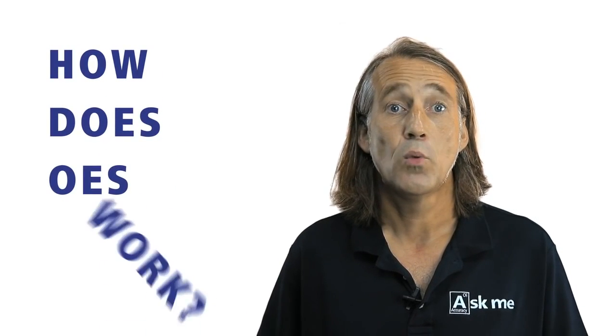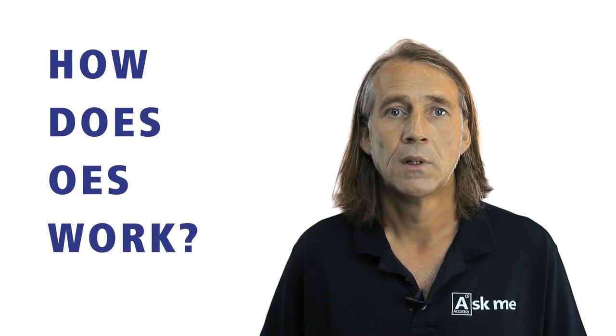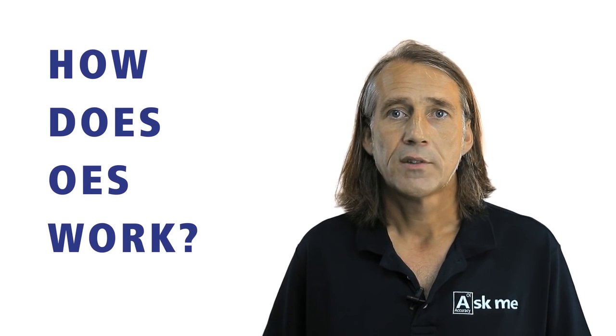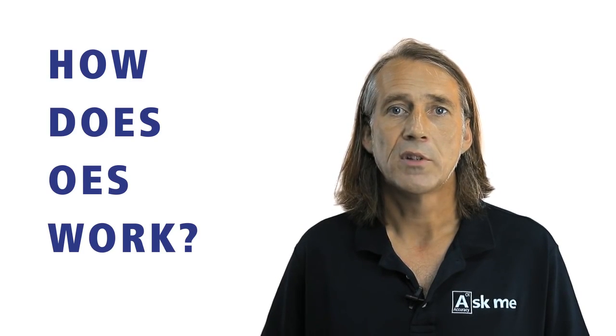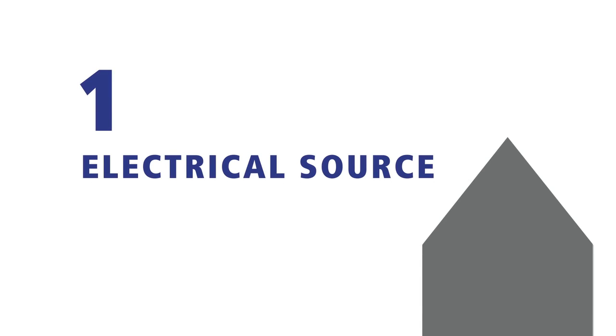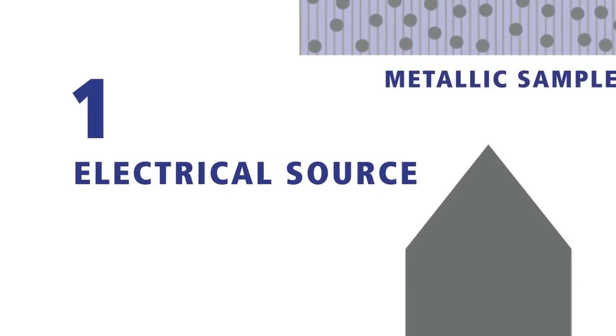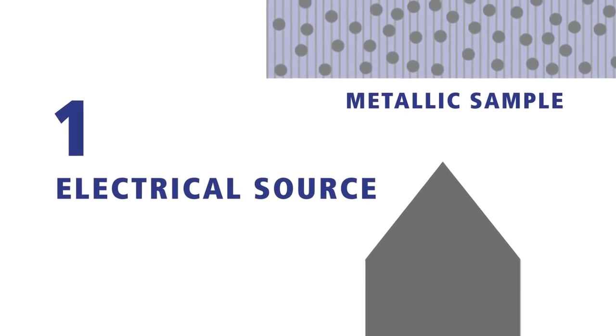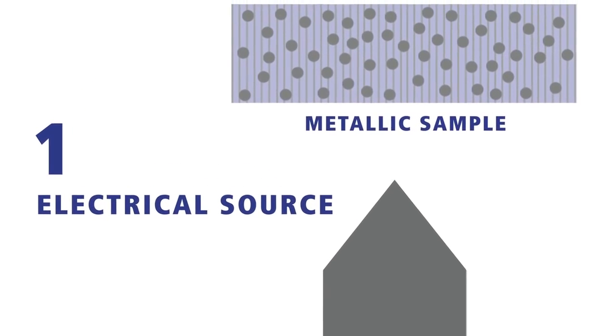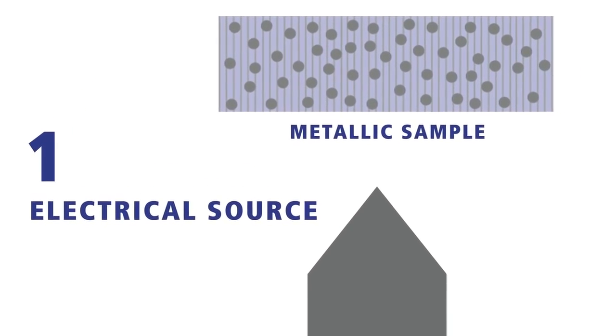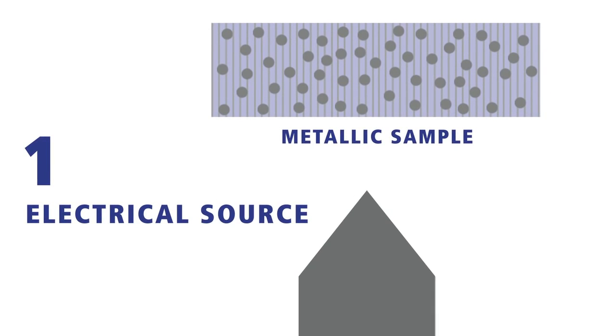So how does optical emission spectroscopy work? All OES analyzers contain three major components. The first is an electrical source. To excite atoms within a metallic sample so that they emit characteristic light or optical emission lines requires a small part of the sample to be heated to thousands of degrees Celsius.